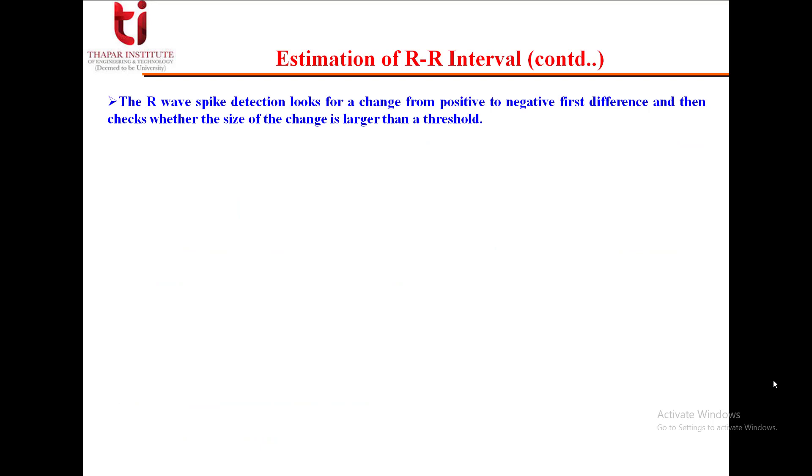The R-wave spike detection looks for a change from positive to negative first difference and then checks whether the size of the change is larger than a particular threshold. If both these conditions are satisfied, then the point at which the change has occurred is marked as an R peak.